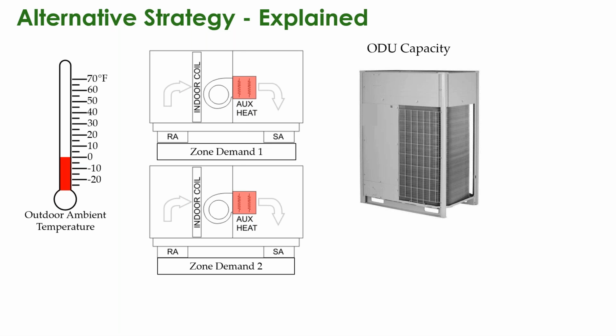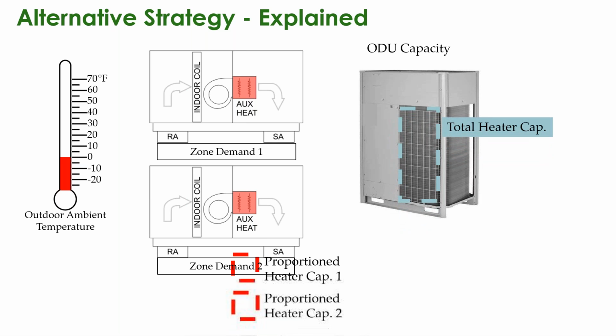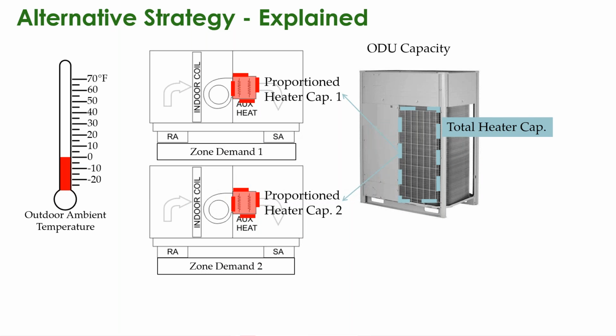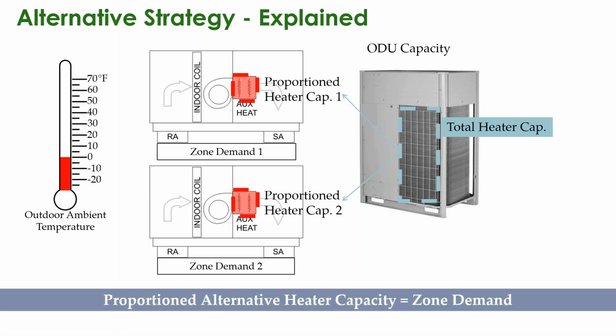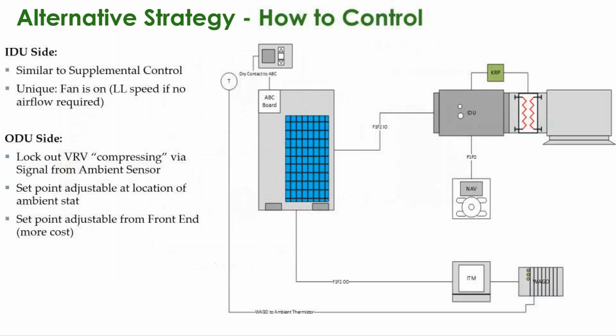Or we've lost enough capacity that comfort is going to become an issue because discharge air temperatures are dropping. At that point, we shut the outdoor unit off and we switch over to the proportioned heater capacity at each individual zone. At that point, that proportioned alternative heater capacity should equal the zone demand. This could also be defined as emergency heat.